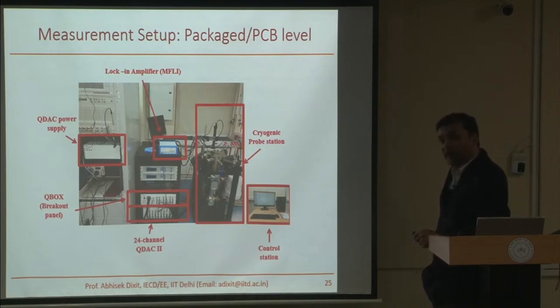There we have installed the RF probes successfully. So yes, RF probes are there, and we have done successful measurements. We have done SOLT calibration.